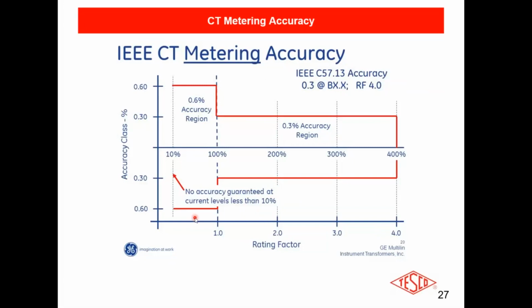The other thing that many people don't recognize is if you oversize your CT, not only does your accuracy go in half, and you may always be measuring at 0.6. So let's say that for 200 to 300 amps, you would actually put 400 to 5s on. You're always going to be measuring at 0.6. And when you go down to 10%, there is no rating. You may not be getting any measurement at all, or if you do, its accuracy is going way, way down.